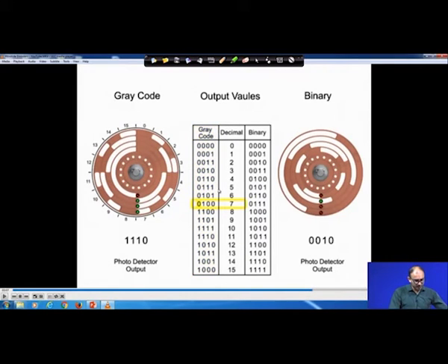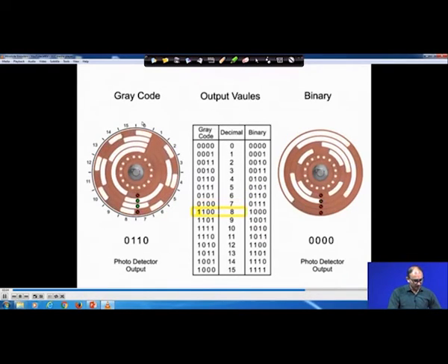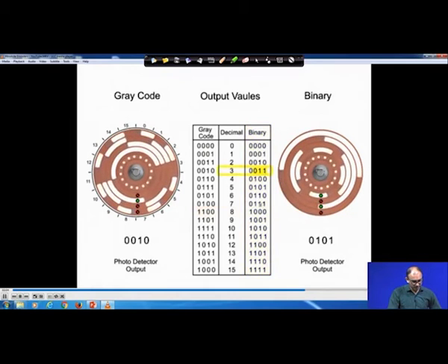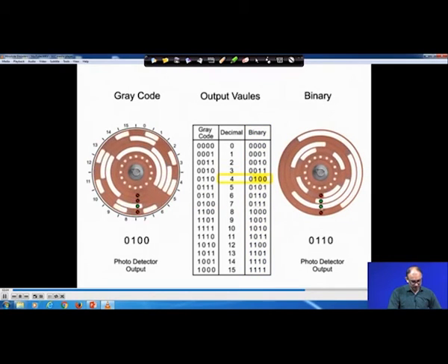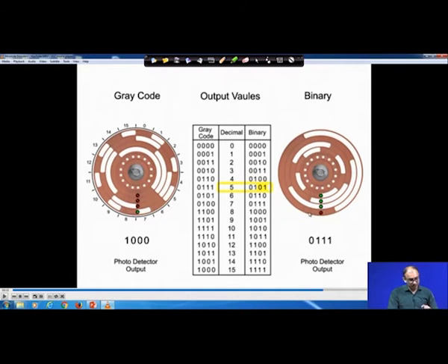Right. So, these are all 3 kinds. This is called grayscale, this is the decimal scale, and this is the binary scale. How is it different in grayscale? You will always get only one output change: when it is rotating, only one signal will change, not more than one. For each and every movement, only one signal changes. But if you consider binary, more than one signal will change with a 22.5 degree change. When it is moving from here to here, more than one signal will change. That is the problem in this case, because accuracy will not be that high.